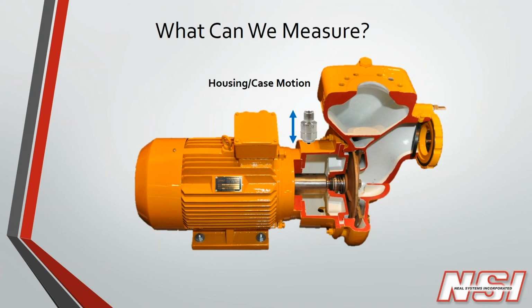And then in the next slide, what I've shown is a picture of a proximity probe mounted through the housing. And so in this case, what we're looking at is relative shaft motion. And that's because with the proximity probe mounted in the housing, while the housing is moving, we're looking at the shaft motion, but it's relative to the position of the probe, which is also theoretically moving. So it's helpful to call this relative shaft motion just so that we remember we're looking at relative shaft motion, not absolute shaft motion.